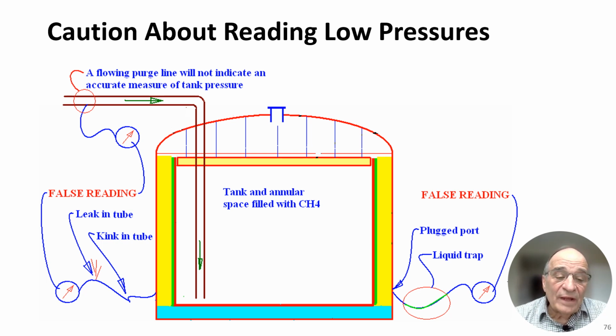Also, you have to be aware that at low pressures, you're very sensitive to having a kink in the pipe or maybe having a liquid in the pipe. A liquid trap would certainly give you a false reading. Also, you have to be aware that reading your low pressure is dependent upon the location of where you're reading it.